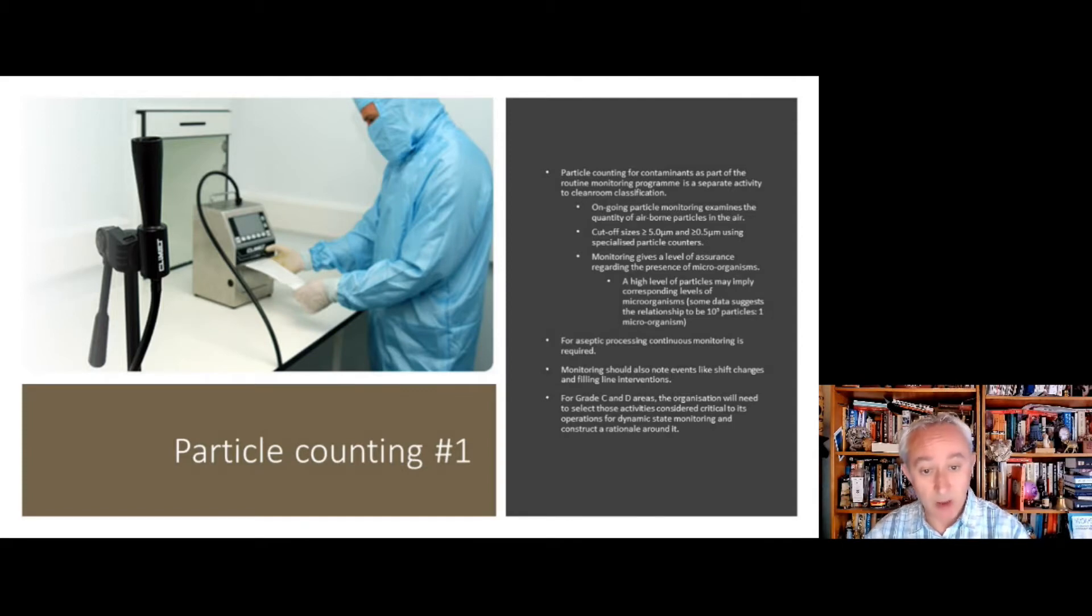It's a requirement to look for particles of two cutoff sizes: greater than or equal to 0.5 micron and greater than or equal to 5 micron. These are cutoff sizes, not discrete particles, so the particle counter will be running in continuous sampling mode.